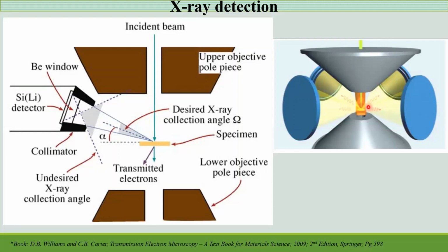Yeah, so such an advanced X-ray detector is possible, and there are some TEMs which have just two detectors instead of 4, but they are placed as close as possible to maintain the takeoff angle and to get as many X-rays as possible without any tilting. So this advancement makes more efficient chemical quantification possible nowadays with TEM.